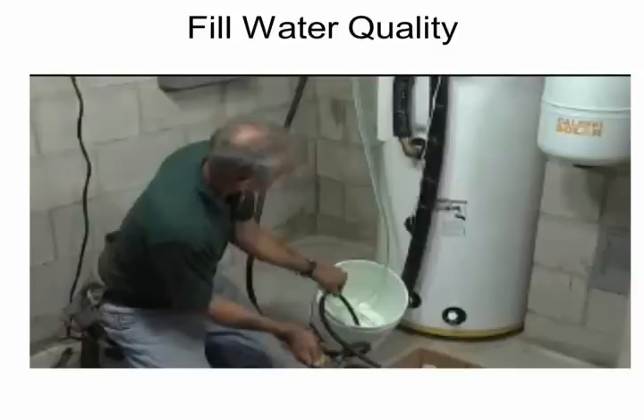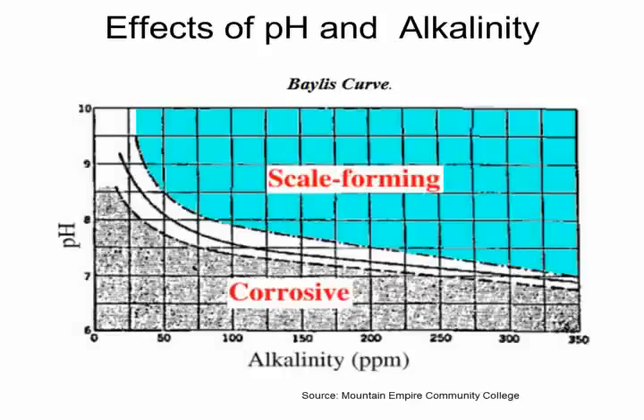So here's Bob filling up a solar thermal system, okay? And if he were to fill this system up with water that was having minerals in it, basically hard water, okay, well, does he still have a problem with perhaps scale forming or corrosion forming? Well, it depends on the pH and the alkalinity, and this is where the two interact with one another. And this is the Baylis curve.